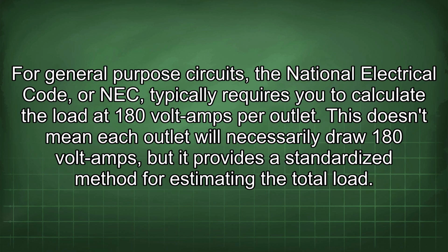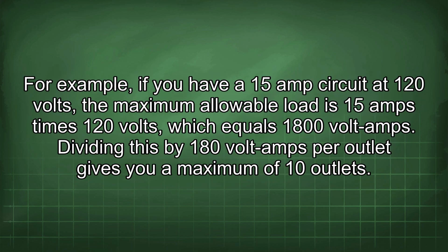For general-purpose circuits, the National Electrical Code, or NEC, typically requires you to calculate the load at 180 volt-amps per outlet. This doesn't mean each outlet will necessarily draw 180 volt-amps, but it provides a standardized method for estimating the total load. For example, if you have a 15 amp circuit at 120 volts, the maximum allowable load is 15 amps times 120 volts, which equals 1800 volt-amps. Dividing this by 180 volt-amps per outlet gives you a maximum of 10 outlets.